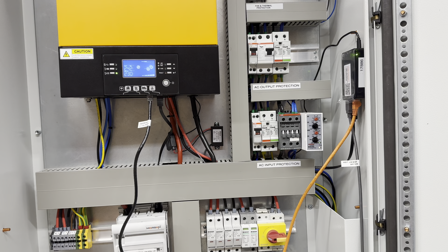If you have more than 3 batteries, it is important to use a Lynx DC distributor from Victron. I'm gonna show you right now how this Victron works. You need to group 3 batteries, the power terminals of 3 batteries to the bus bar. Then the other 3 batteries are linked to the same bus bar, and the output of the DC Lynx distributor is connected to the Mersen fuse disconnector. This setup with Lynx is very important when you have more than 3 batteries, and you need to group them separately to share the current of the batteries.